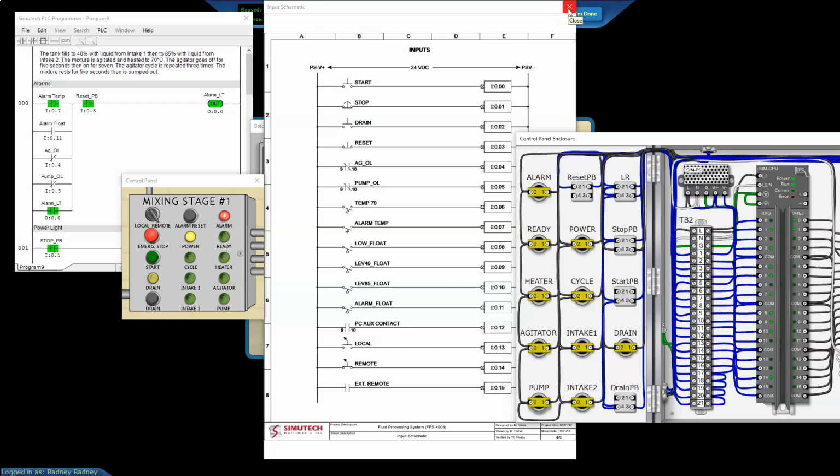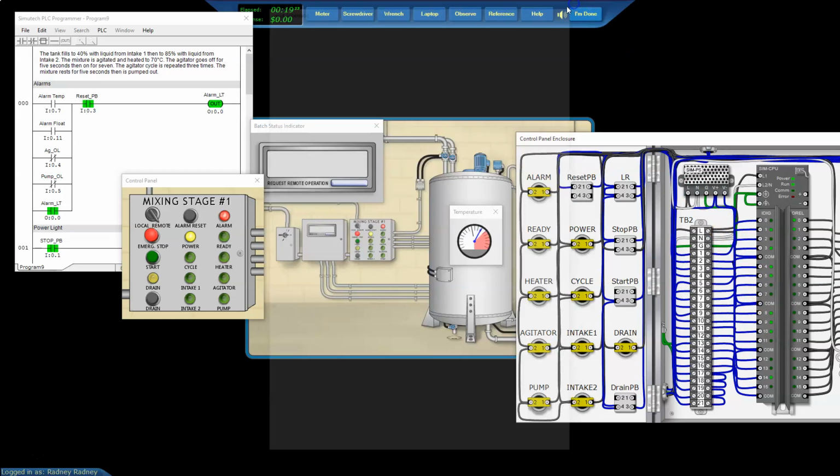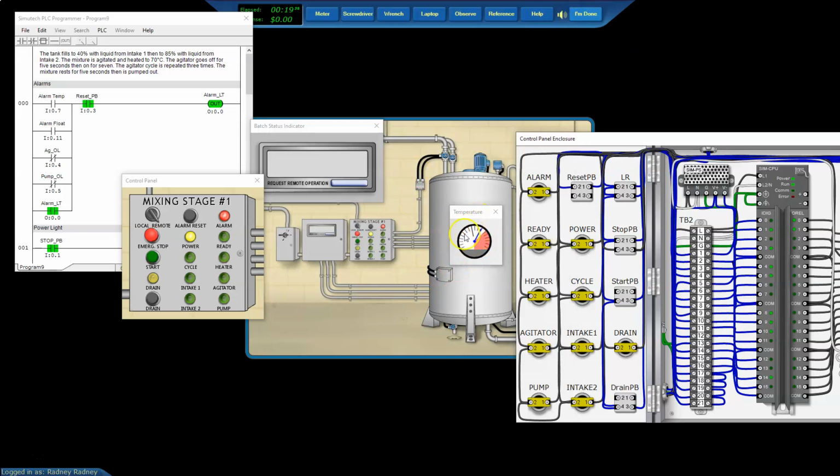And these are not intelligent in that they know 70 plus or minus an amount. They know less than 70, or 70 or greater, is the way this particular switch works. So bit 6 never turned on. Now we can verify that easily enough. Let's remember, we know that 6 is 70 and 7 is above 70. That gets us an alarm state. So we see 6 has cooled down enough, it's no longer coming on, but we still are above the 70 degree mark, so it should be on.